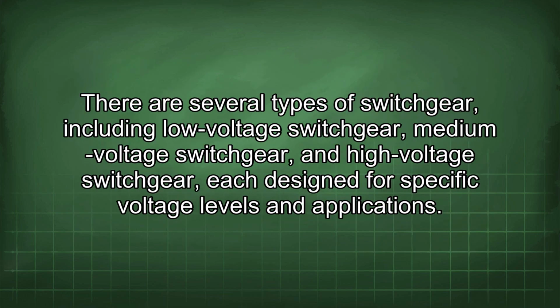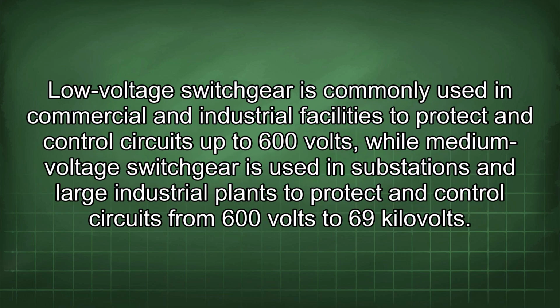There are several types of switchgear, including low-voltage switchgear, medium-voltage switchgear, and high-voltage switchgear, each designed for specific voltage levels and applications. Low-voltage switchgear is commonly used in commercial and industrial facilities to protect and control circuits up to 600 volts, while medium-voltage switchgear is used in substations and large industrial plants to protect and control circuits from 600 volts to 69 kilovolts.